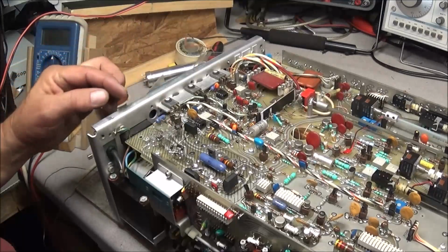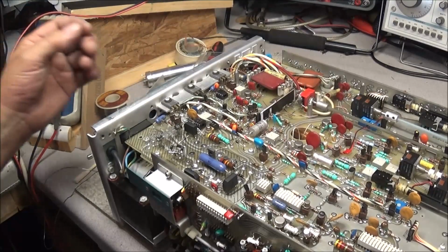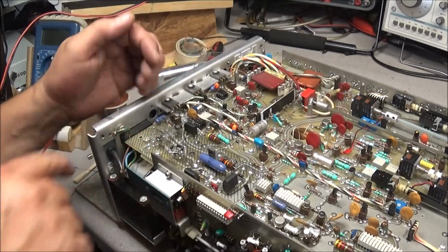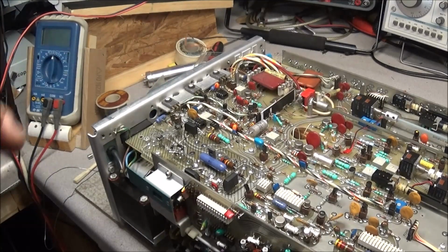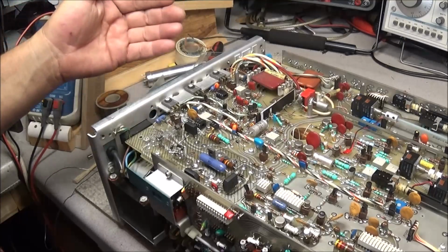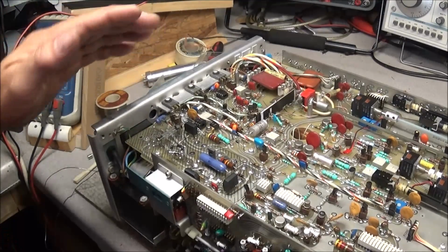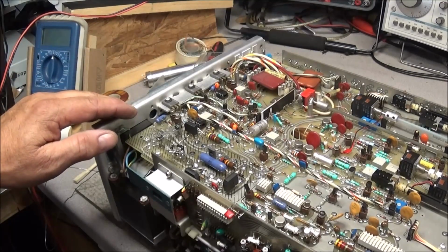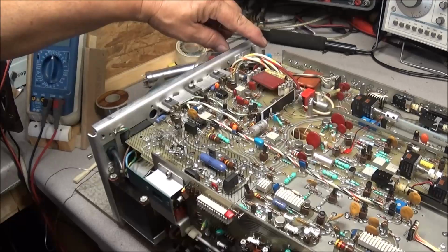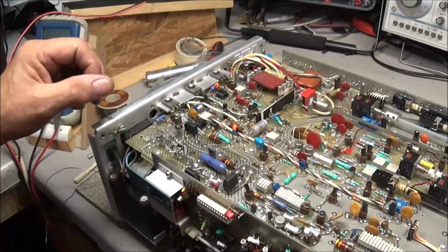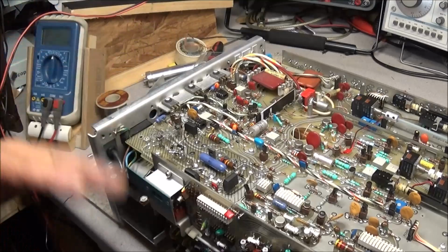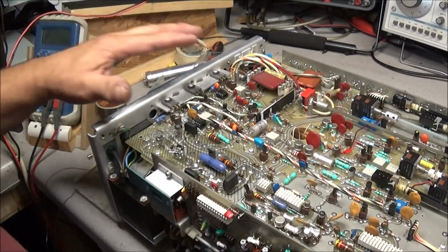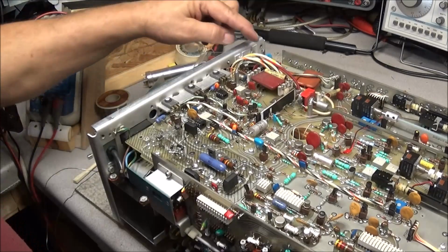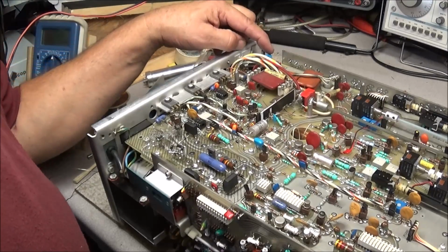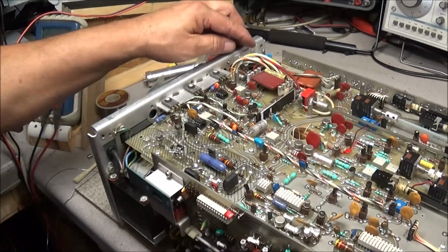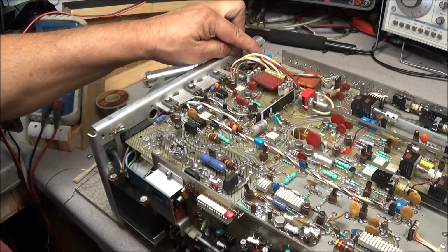Back in the back, I've noticed that this fuse has blown again, and I believe it's F1419. And usually if it blows, that means there's a cap somewhere down the line that has shorted. And if we look over here on this side, you notice I have the high voltage exposed. Now make sure your scope is off, not plugged in, no power, because this is dangerous voltage over here. And over here is C, I think it's 1419. I have to look back on the schematic.